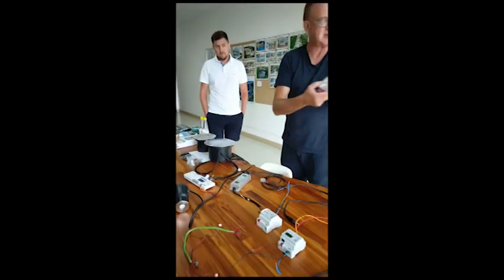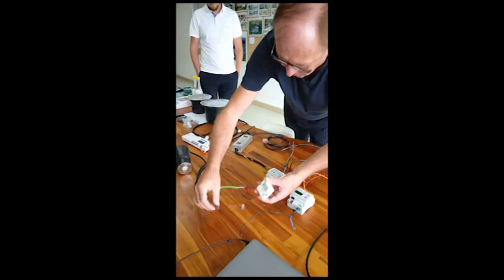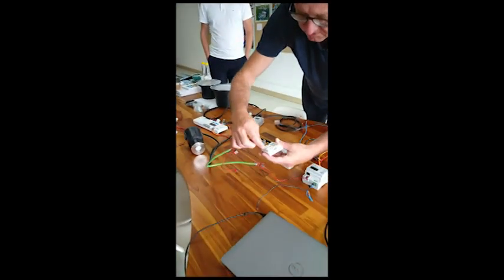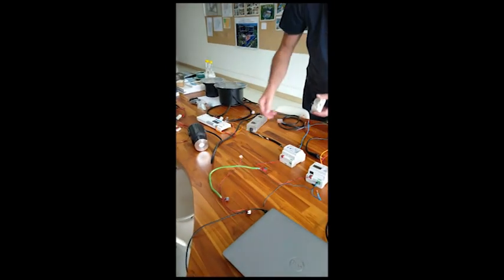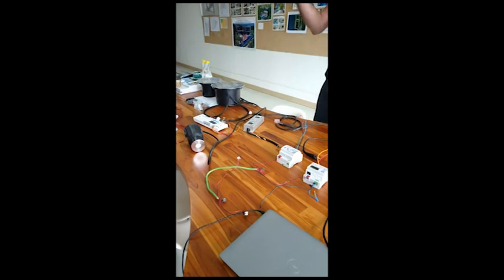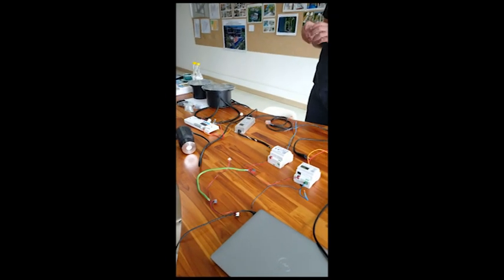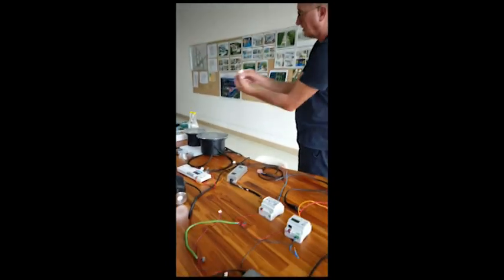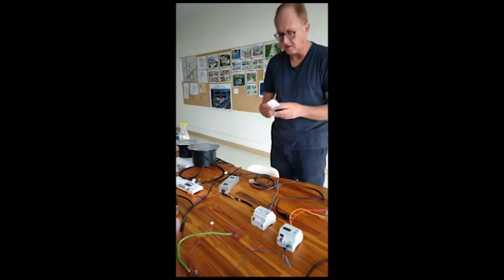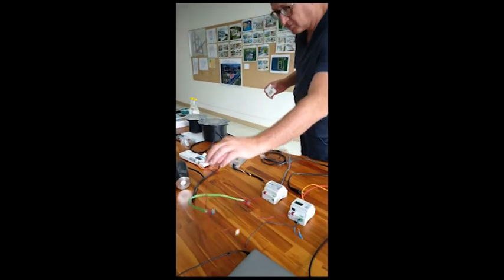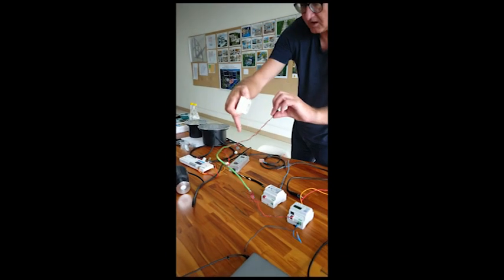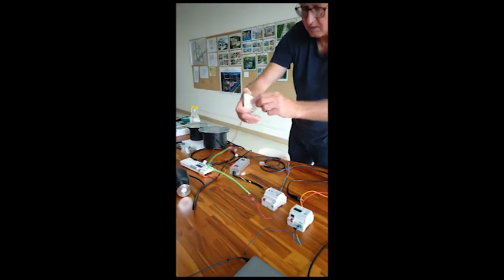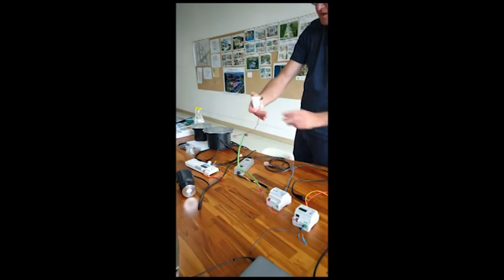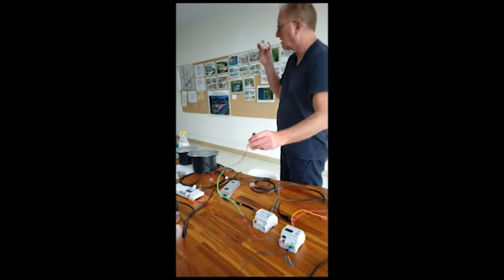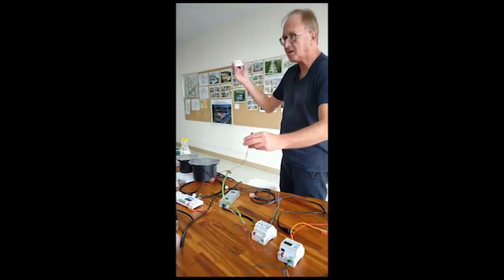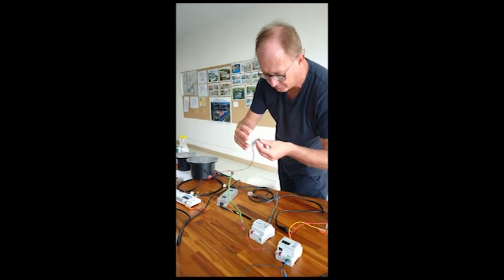Then you connect basically any switch that comes to the wall. You can put it wherever you want, it doesn't matter, it's all the same. On the wall, it just needs one of the boxes I sent you, a big one, with a frame, and you click the device into the frame. Installation-wise, you just run this green cable around, going from here to here, boom, boom, boom. You can do it whatever way you want, and it doesn't matter whether it's a humidity sensor, wind sensor, or switch - every KNX device just clicks in here.